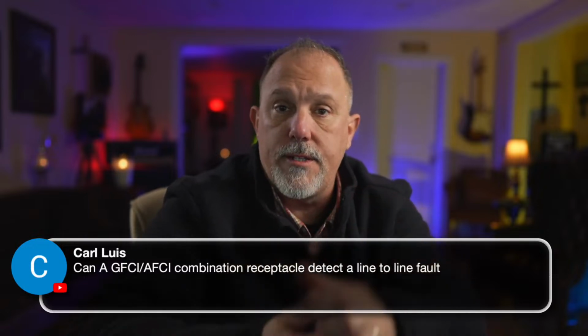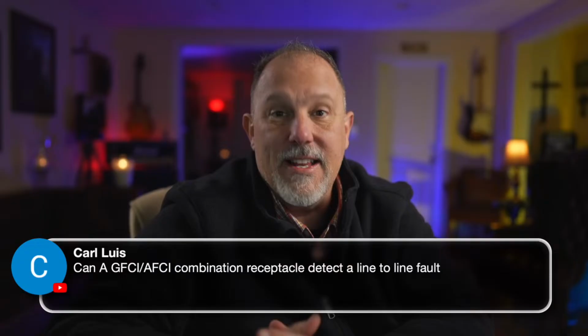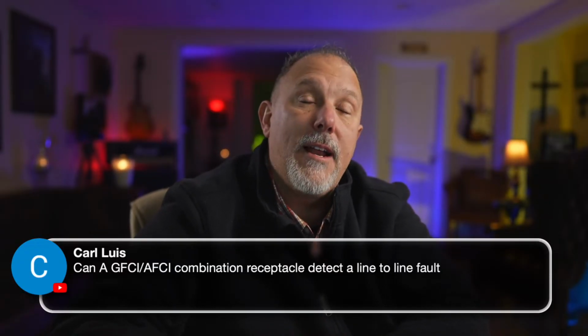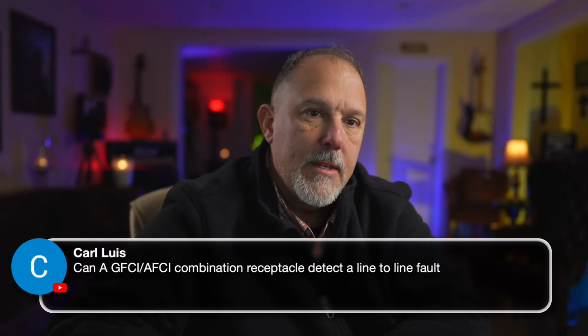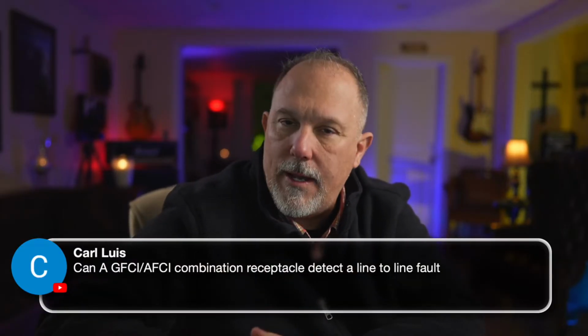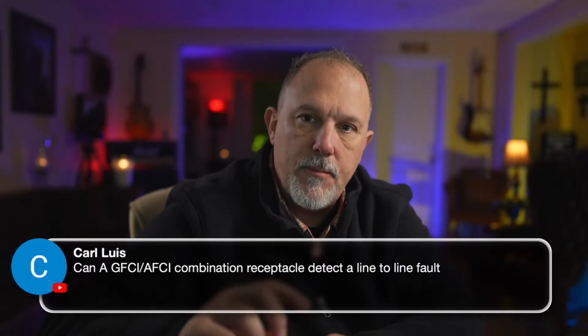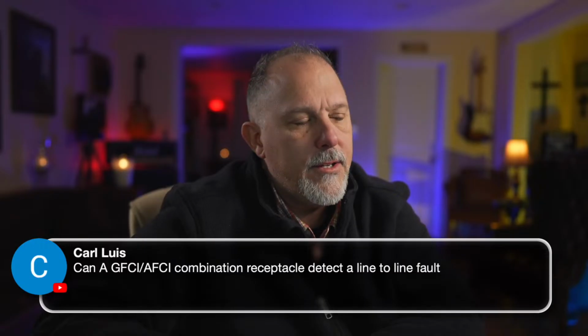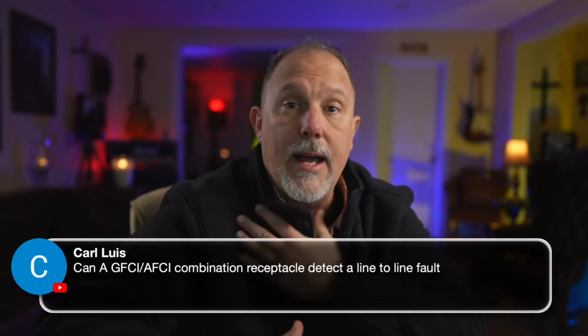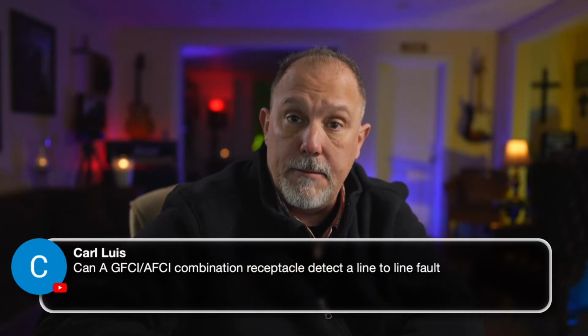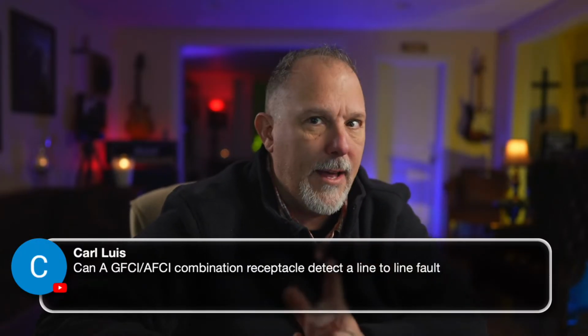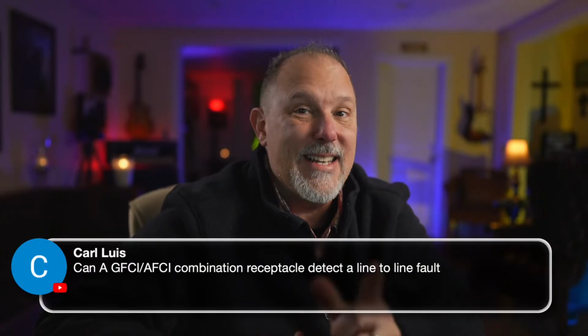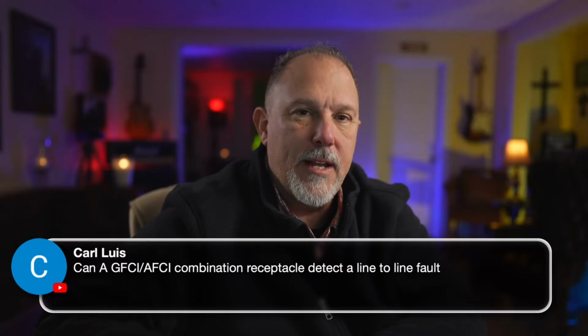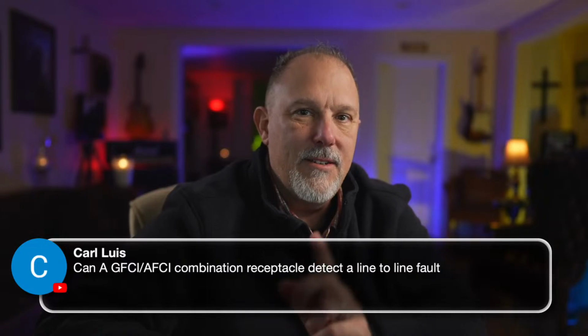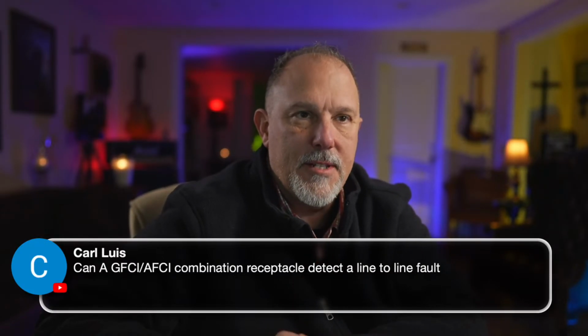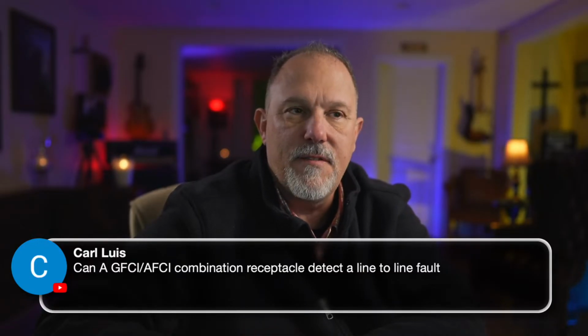So Carl, if I take two wires and short them, geez, I'm looking for the words. If I put a wire nut on it and short it, which I did once, on the advice of an electrician friend of mine, there was a pair of conductors I pulled out of the ceiling, and all the breakers were off. And I was putting things back, and he said, do me a favor. I said, what? He goes, you know those two conductors? Short them and put a wire nut on them. And I was like, well, why? He goes, we don't know what breaker those are off of. And I was thinking that they were just wires abandoned in place. And I said, well, those are wires that are abandoned in place. He goes, we don't know that. And I said, well, that's a very good point. So I did exactly what he told me. And there was one breaker inside my panelboard. The moment I closed it, it opened. And I knew exactly what circuit that was. And then I was able to fix the problem. But that electrician was a very smart dude.